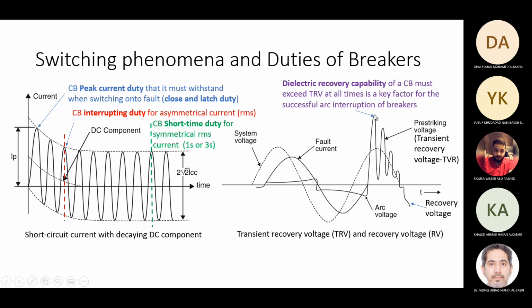Is the breaker able to withstand that transient voltage? This is called the dielectric recovery capability of the breaker. The insulation medium, which is oil or gas, also has a dielectric strength. If the dielectric strength of the insulation is lower than this, then the breaker will fail to open, and you'll have something called restriking. The current will still continue because of arcing. I'll come to this later, inshallah. So this is another aspect we should look at, the transient recovery voltage, especially when we are talking about generator breakers and high voltage breakers.